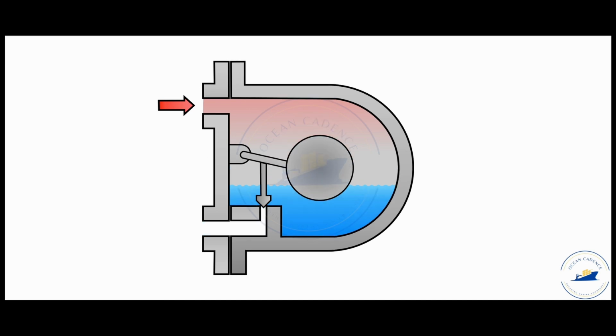The advantage of this steam trap is that it has a large volume dealing capacity. That means once the float is lifted up, it will allow a high amount of discharge to occur. But by virtue of the mechanical moving parts as well as the ball weight itself, the operational time of the mechanical steam trap is a little higher as compared to the other designs. And also because of the moving parts itself, it requires a little more maintenance than the other designs.